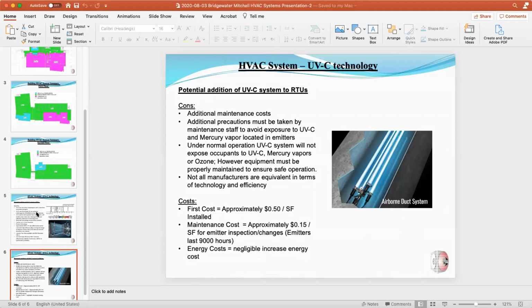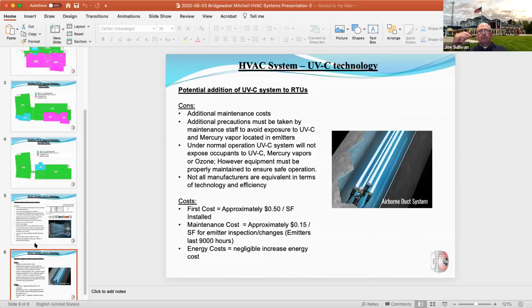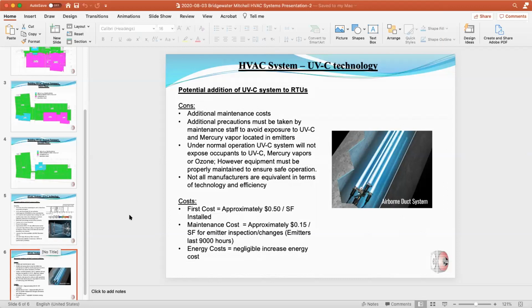So what we did here, I just gave an overview of that UVC technology, which, out of some of the buzzwords you hear, is probably the one we'd recommend, because it's likely the easiest to implement and has the lowest energy impact. However, the cons: there would be additional maintenance costs. As I mentioned, there's mercury vapor, so for any maintenance you've got to avoid exposure and make sure it's completely de-energized. Under normal operation, these would be safe. However, if there was any malfunction, make sure it gets de-energized. And then be sure that whichever manufacturer, you've got a couple of equivalents that could be bid as equals, because not all are equal.